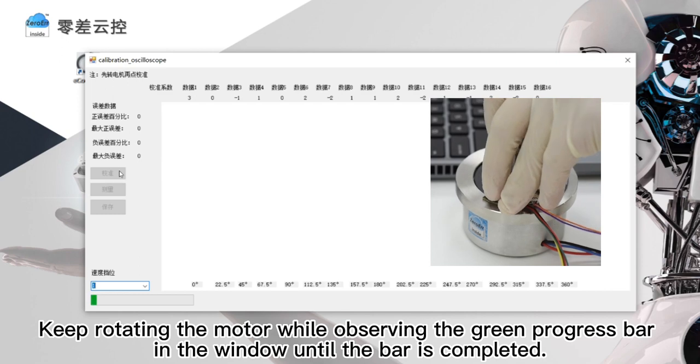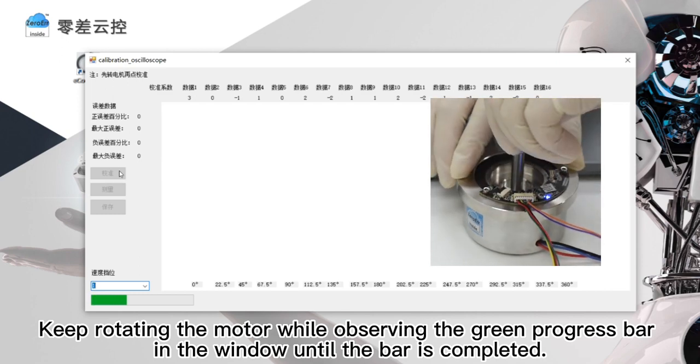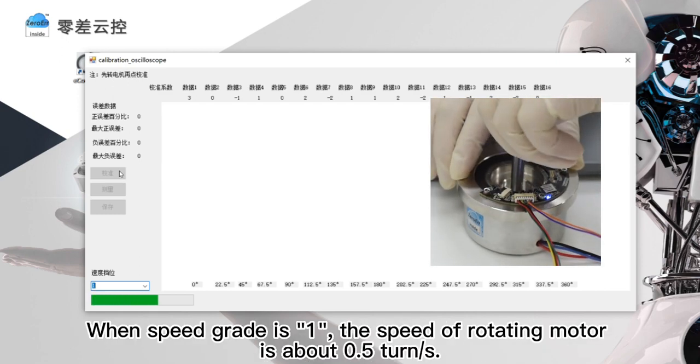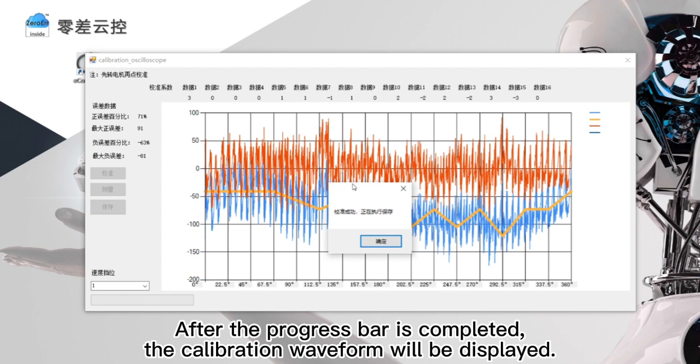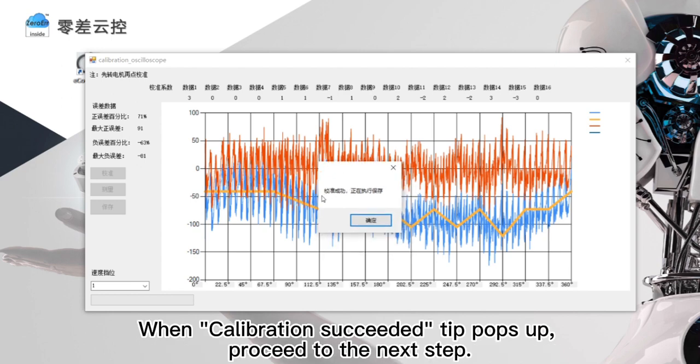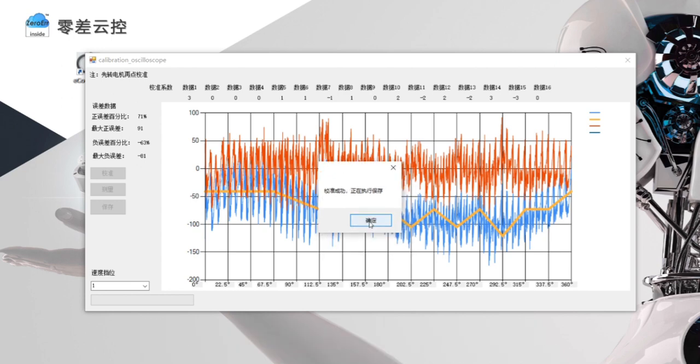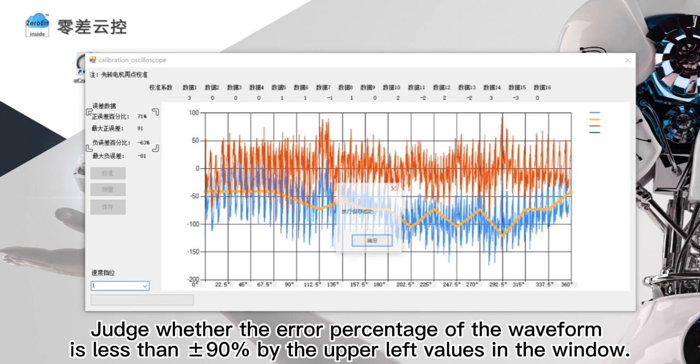Keep rotating the motor while observing the green progress bar in the window until the bar is completed. When speed grade is 1, the speed of rotating motor is about half a turn per second. After the progress bar is completed, the calibration waveform will be displayed. When calibration succeeded tip pops up, proceed to the next step.